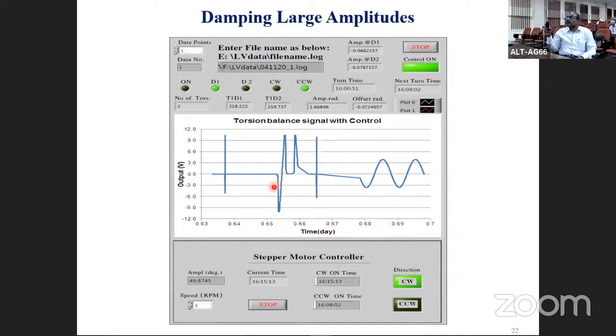Now we see on the horizontal detector, which was earlier like this, it has become this way — more or less on the detector, but going out of it. This is partly because your stepper motor has a certain step size, 1.8 degrees, further divided by a gear ratio of 9, which gives 0.2. So you cannot control beyond 3.5 milliradian — if you go one step beyond your control, it leads to going out of the detector.